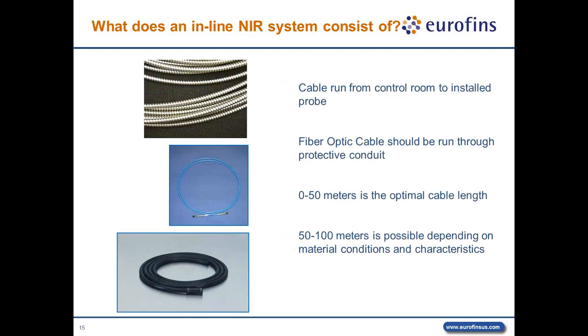The fiber optic cable can be run out from the control room through conduit to the desired location for analysis. While the NIR light can easily travel through the glass threads of the cables, there is still some energy loss along the way. A 0 to 50 meter range is the optimal range for the fiber optic cable length to preserve the signal strength. However, there are situations where that range can be extended to 100 meters. Much of this depends on the parameters being analyzed and the characteristics of the material being tested.